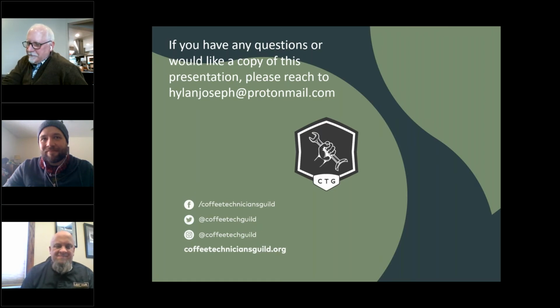Caleb Leach asks, why is 208 considered more efficient than 240? It seems like less amps at higher voltage would be efficient. Any takers? Okay. Generally, I like high voltage. Espresso machines love to live at 240, 245. They heat up faster. You're delivering more power more efficiently to the elements. You run less risk of voltage dropouts. It's pretty rare that you'll get like 280 volts to a machine, but typically, 240 is a very happy place.